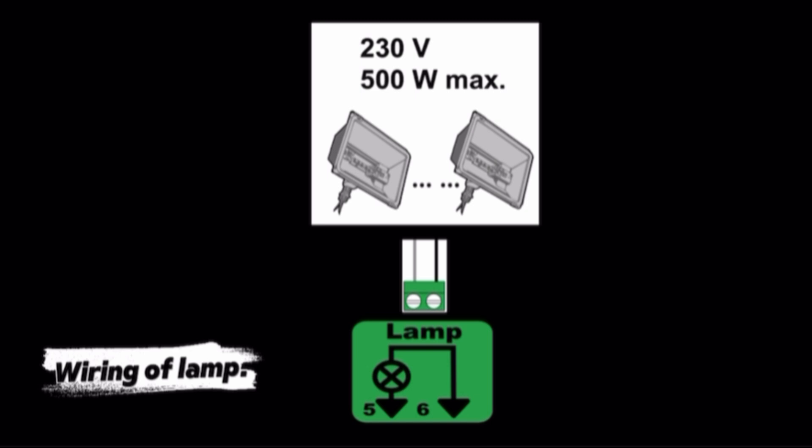Wiring of lamp, terminal 5 and terminal 6. The output is 230 volts and maximum 500 watts, protected by 5 amp time delay fuse.